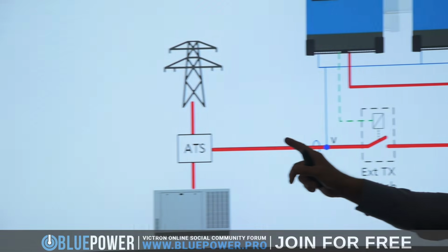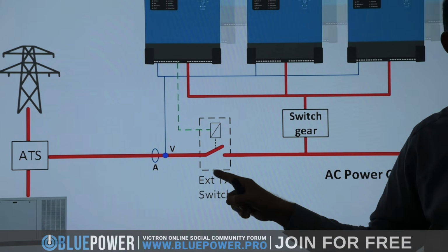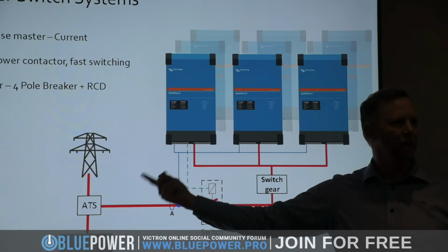Basically, the CT connects to each master and measures the current, and then the AC input is connected to the input with a thin cable just to measure the voltage. And that tells the system to close the transfer switch to connect to the grid or the generator.